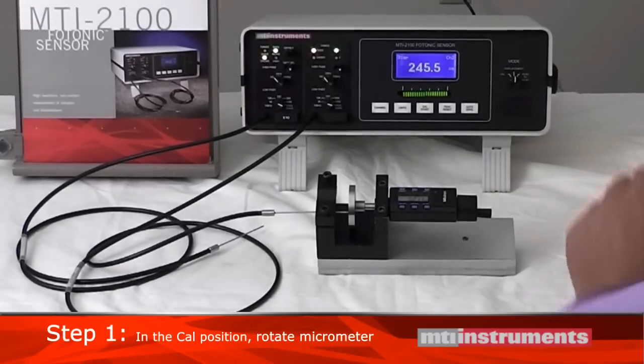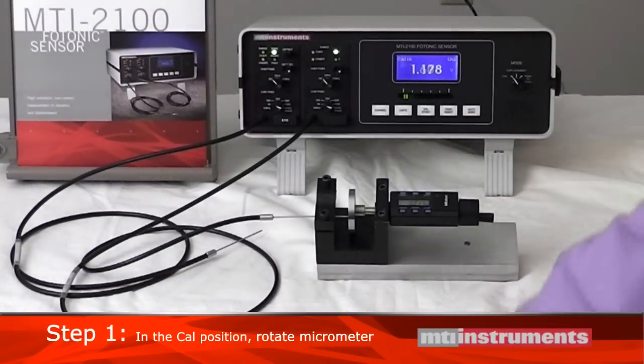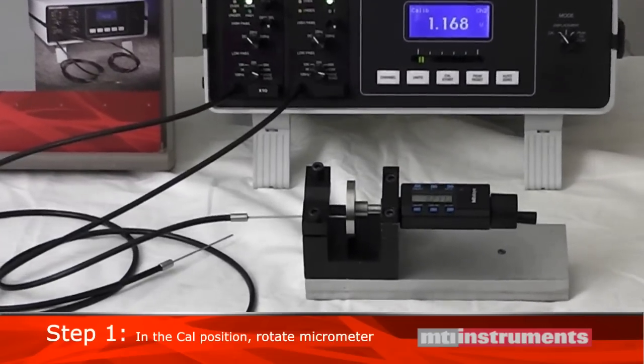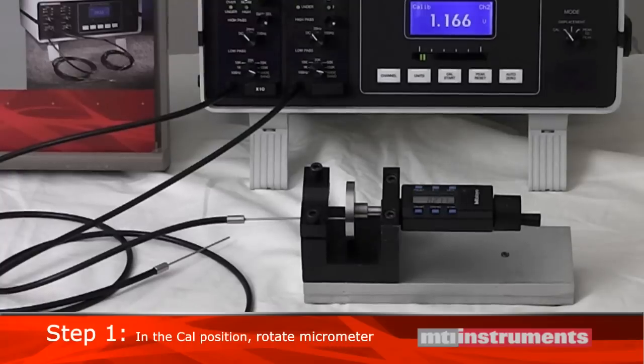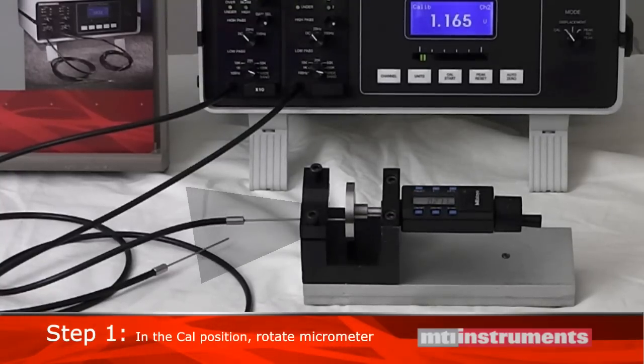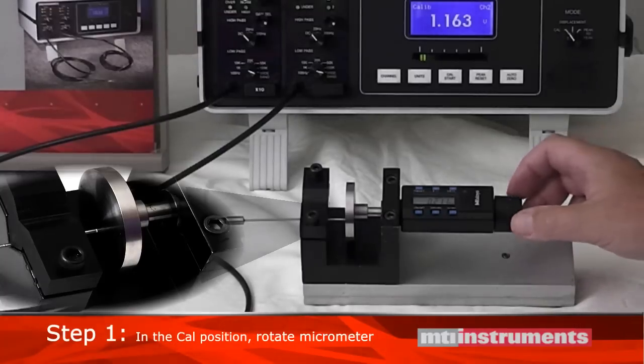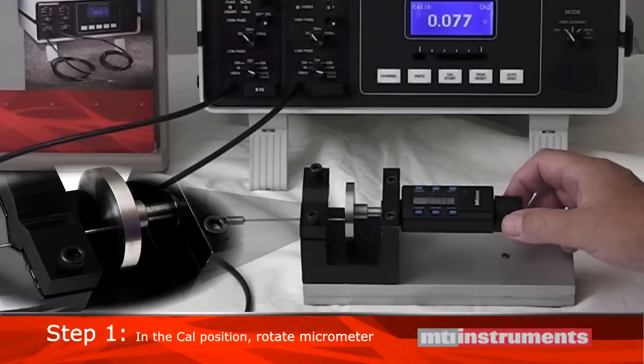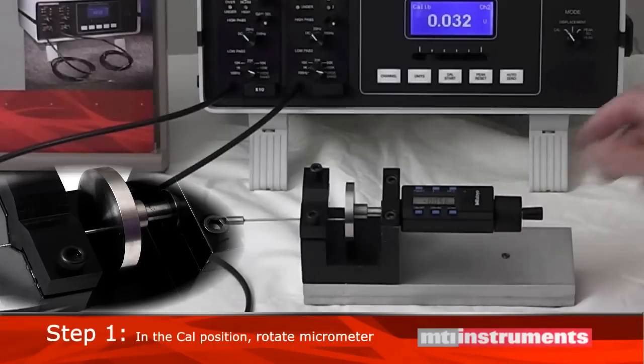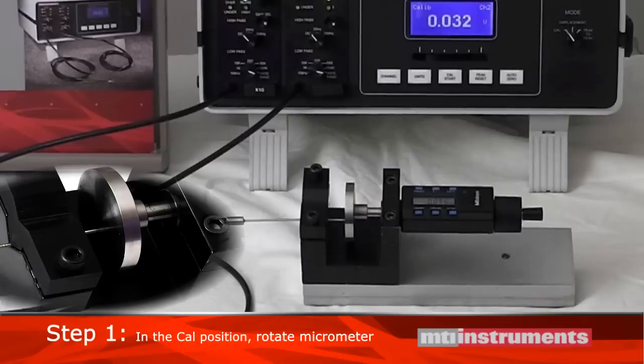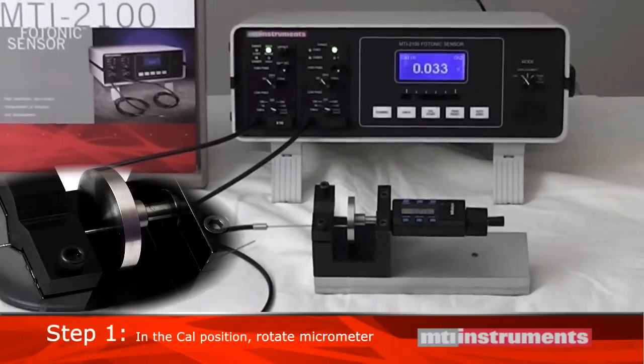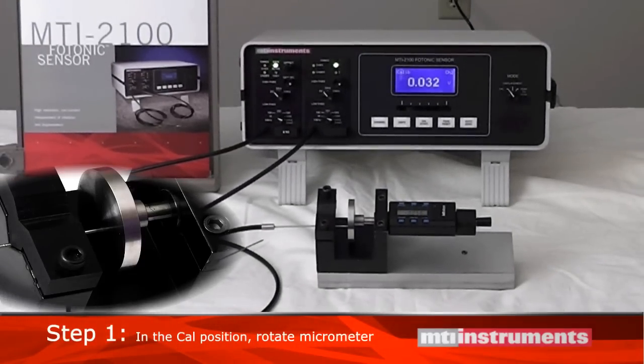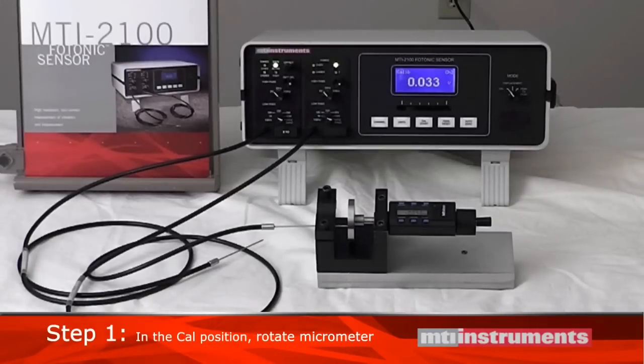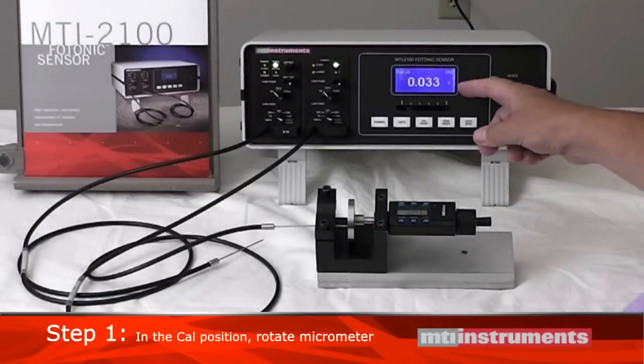First, rotate the mode switch to the cal position. Next, rotate the micrometer clockwise to gently contact the target disc and to completely cover the light from the probe tip. Be careful that excessive force is not applied to the probe tip with the micrometer. When the probe tip is flat to the target with no probe tilt and none of the transmitted light is getting back into the received fibers, the display reading should indicate 50 millivolts or less.